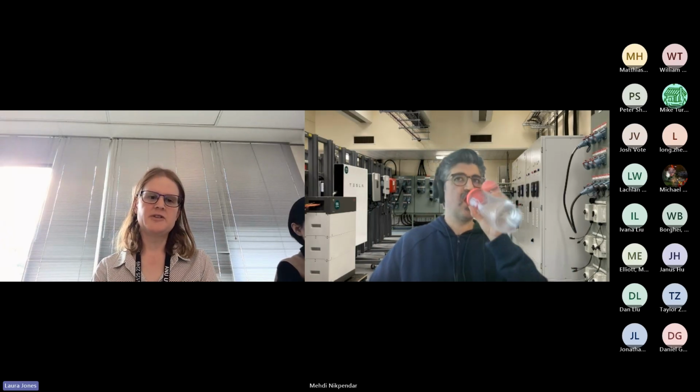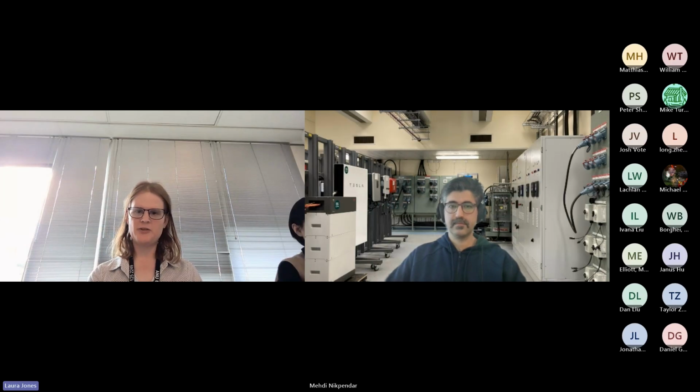I think we talked about the lab. We can host devices in our lab, but we expect that most people will use their own facilities, in line with what South Australian Power Networks did. The power meter, there are some accuracy requirements in TS-5573. I don't think they're particularly onerous. One of the key parts is that TS-5573 has ramp rates in it, and that wasn't something that the previous version tested for.